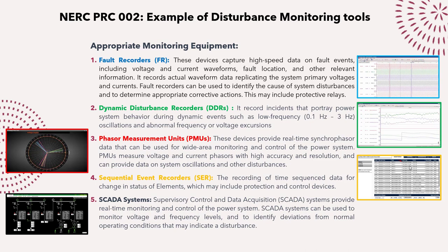The sequential event recorder captures tight-sequence time-stamped data for changing status of elements, including protection and control devices such as isolators, breakers, main-1 protection, main-2 protection, or other protection systems. The SCADA system — supervisory control and data acquisition — has a slightly slower data storage rate compared to the faster devices. It provides real-time monitoring and control of the power system and can be used to monitor voltage and frequency levels, identifying deviations from normal operating conditions that may indicate disturbances.